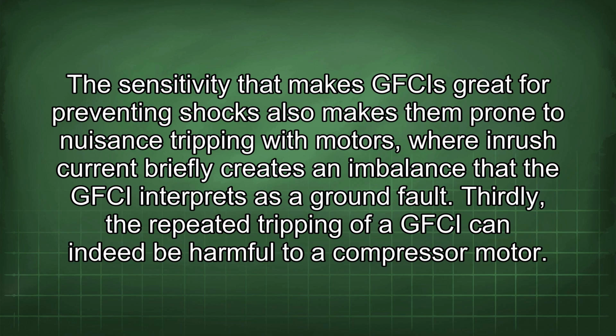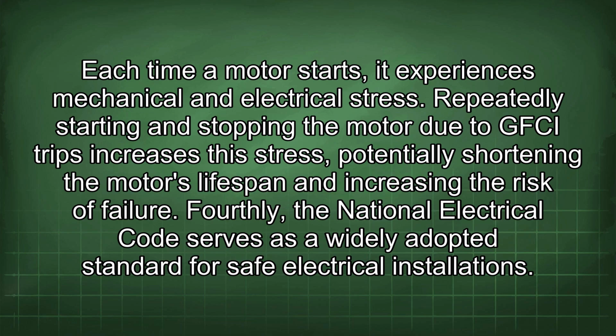Thirdly, the repeated tripping of a GFCI can indeed be harmful to a compressor motor. Each time a motor starts, it experiences mechanical and electrical stress. Repeatedly starting and stopping the motor due to GFCI trips increases the stress, potentially shortening the motor's lifespan and increasing the risk of failure. Fourthly, the National Electrical Code serves as a widely adopted standard for safe electrical installations.